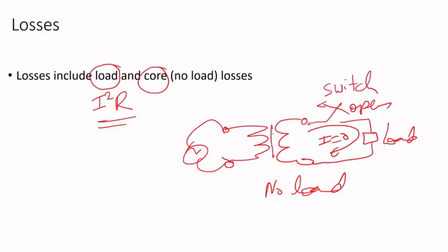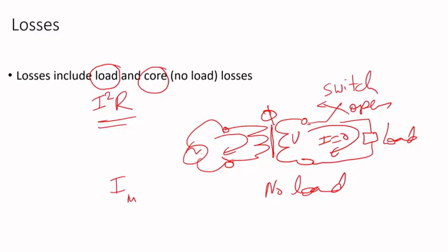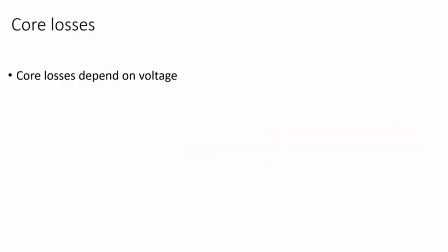Even if the current is zero on the load side, when you energize the transformer some current will circulate - the magnetization current which will establish flux in the core because it's going to induce some voltage in the secondary. So there will be some core losses even if the transformer is operating under no load.